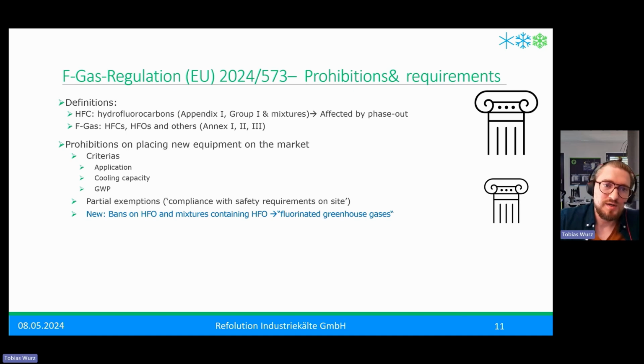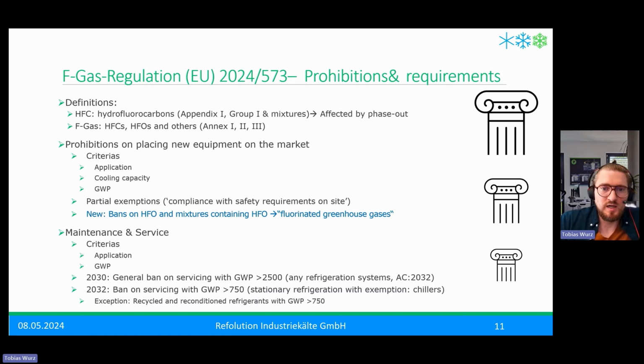New in this regulation is that in the old regulation we had, okay, HFCs are forbidden or HFCs are limited to a special GWP. Now in this new regulation, in some applications or prohibitions, completely F-gases are forbidden. For example, mixtures with HFO that were used as retrofit in the past are now forbidden too in some applications. So if you have an HFO mixture with GWP higher than 750, it could be that these units are forbidden now in the next years.